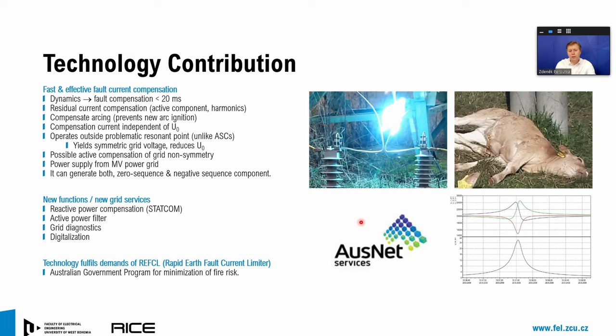We came with new features to the grid, where we are combining the earth fault compensation together with reactive power compensation under no fault operation of the grid. We can secure active harmonic compensation. We can act like an active power filter. Because we behave like a fully controlled current source installed in the system, we can provide new grid diagnostic features. And we offer the grid several functions for digitalization.